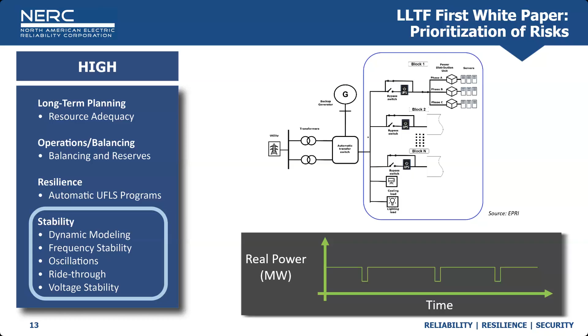We can see under fault type events sometimes a reduction of active power consumption. On the generation side, that is largely associated with momentary cessation of injection of current. We can see something very similar on the large load side, where they will cease the consumption of current as they are moving into their backup generators, and they've changed the source of their power in order to transfer into their backup generators. Now, all of this disturbance behavior affects the stability of the remaining bulk power system. And so our alert identifies areas where the transmission planners and planning coordinators need to study this, as well as areas to ensure that any stability concerns are fully addressed within every entity's respective environments.